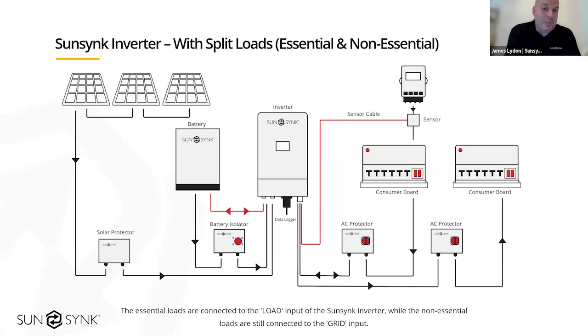So, most installers, if it's a domestic property where there's not many power outages, but somebody wants access to power if there is going to be one in the future, you could essentially install a double socket out of the inverter for the homeowner to then go, with an extension lead, let's say, and give them access to power. Or you can wire in a dedicated circuit. That dedicated circuit, maybe the lights, Wi-Fi, the fridge, if there is a power cut, that will remain powered if there is an outage from the batteries and the PV. Obviously, there are different earthing arrangements required, but we do have that dedicated output built into the inverter.